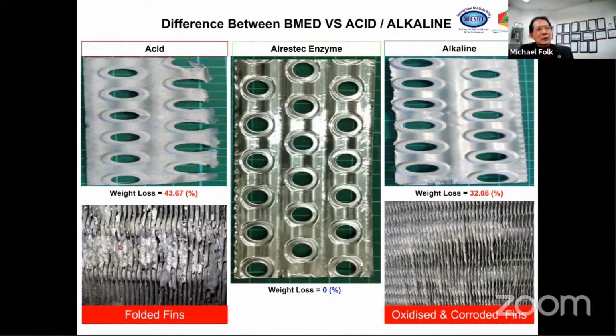On the bottom left-hand side, you see what happens when the coil has been corroded: folded fins, whereby the fin became so thin and soft that it will bend. When it's bent, the airflow is not good, and it will start to use more energy to blow out the satisfactory amount of air that is required. At the same time, behind the folded fins, biofilms will still be there, capturing more fungus, bacteria, and so forth, which is why sometimes, even after a chemical clean, you can still smell the mold smell because it has not been removed.